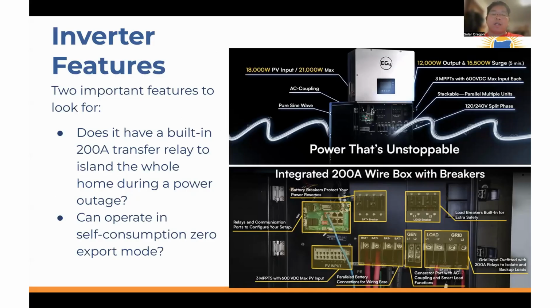How the inverter does that is it has current transducers on the main power wires coming from the electric meter, and it senses which direction the current is going, whether it's coming in or going out, and then adjusts how much inverter capacity it's going to produce on a second-by-second resolution, making it so the number of amps going out and in is zero. That results in self-consumption zero export mode.